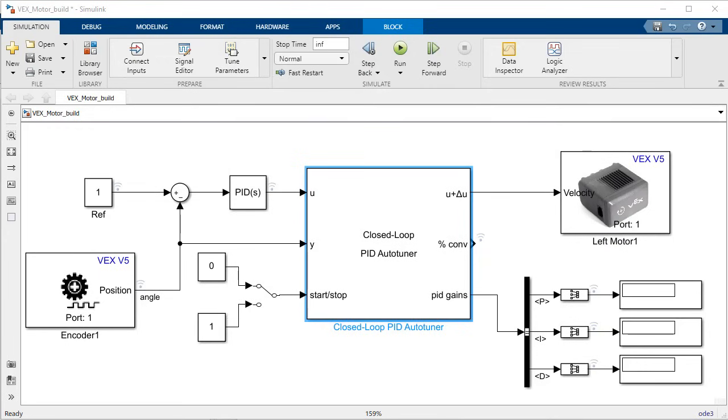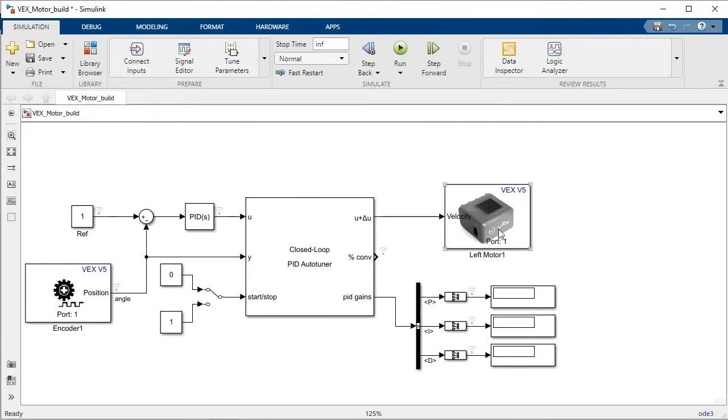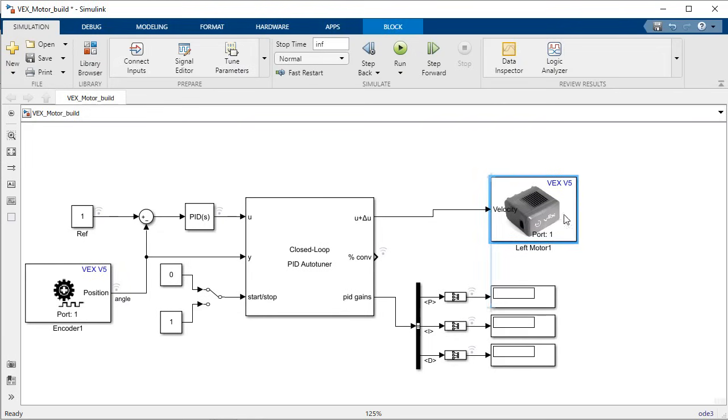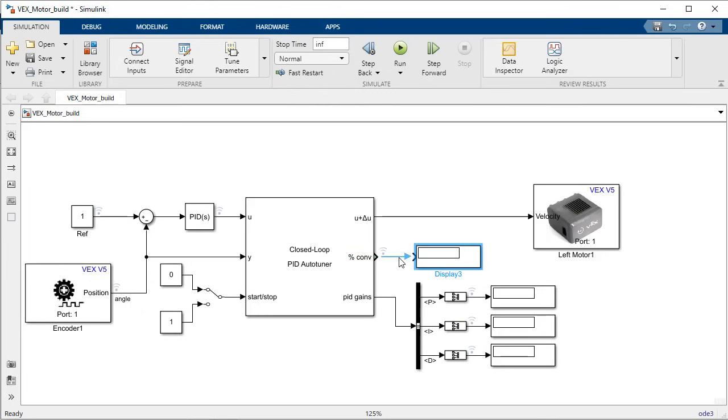To determine whether the test is successful or not, you can monitor the test convergence using the second output. Once we start the test this value should converge quickly, and once it gets close to 100% you can stop the test and record the PID gains calculated.